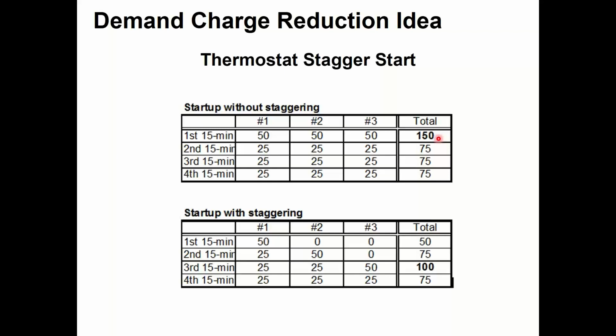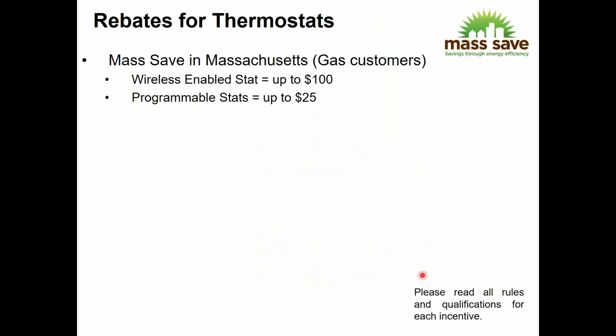If I started staggering them out, I can break that down. So I might have 50 if it comes on with just one unit, boom. And then that unit continues running at 25. The next guy comes on with 50, that's 75. And then when the third guy finally kicks on with his 50 inrush, I have 25, 25, and 50, so it's 100. So I can make my inrush lower by staggering the start of these guys. Some of the utilities have rebates for thermostats as well, for programmable thermostats.